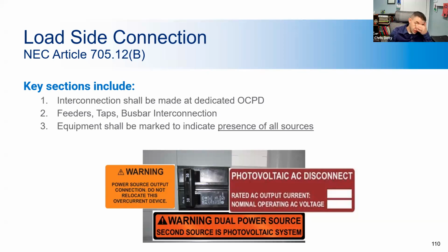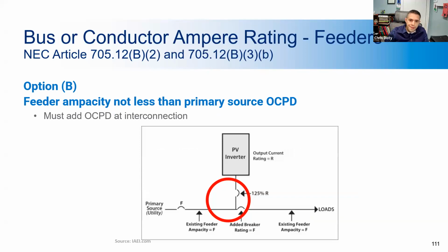And you need a bunch of labels in this situation, which you can see here. Here's a not super common system or configuration, but you might see it. So here's feeder taps, which are a type of interconnection that require special consideration. It's sort of like a hybrid load side connection. They have the potential to add additional available current to conductors and bus bars, and we need to consider this. So in this case, in order to protect the conductors from additional PV current, an additional overcurrent protection device must be installed. This is covered in Article 705 of the code.